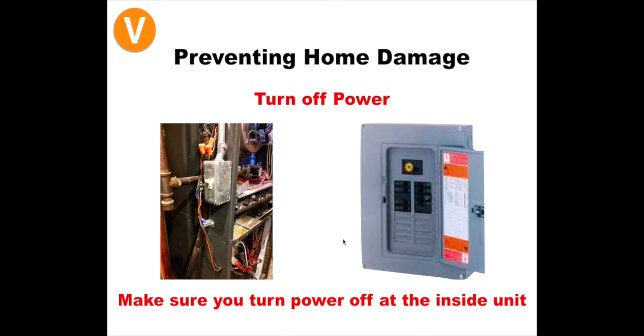Make sure, if you're going to turn off the breaker, I like to let the system run so the fan is still running and you can hear it. When you get the correct breaker turned off, that fan will stop running inside the home, confirming you have the inside unit's power turned off. Whether it's the switch or the breaker, I don't care, as long as you get the correct power turned off, and that can save you a lot of headaches when it comes to fuses and transformers.